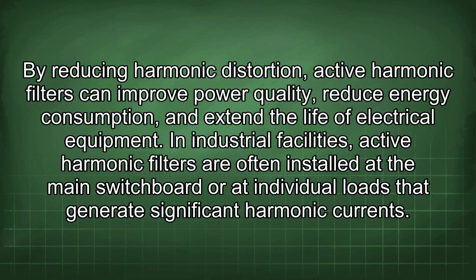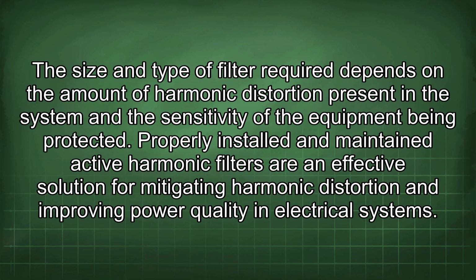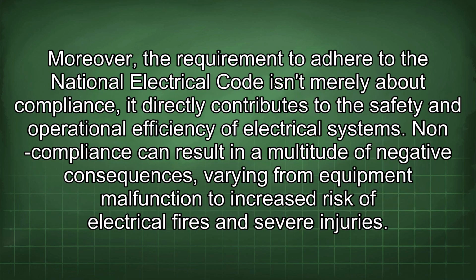By reducing harmonic distortion, active harmonic filters can improve power quality, reduce energy consumption, and extend the life of electrical equipment. In industrial facilities, active harmonic filters are often installed at the main switchboard or at individual loads that generate significant harmonic currents. The size and type of filter required depends on the amount of harmonic distortion present in the system and the sensitivity of the equipment being protected. Properly installed and maintained active harmonic filters are an effective solution for mitigating harmonic distortion and improving power quality in electrical systems. Moreover, the requirement to adhere to the National Electrical Code isn't merely about compliance, it directly contributes to the safety and operational efficiency of electrical systems.